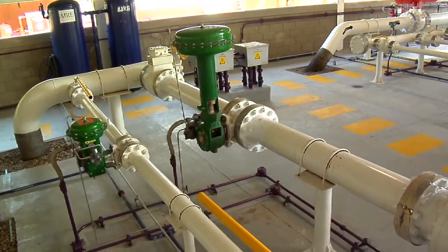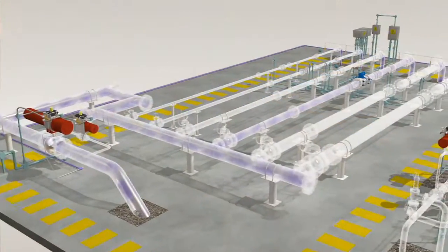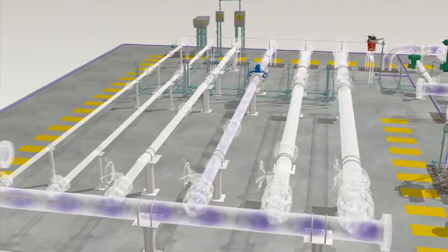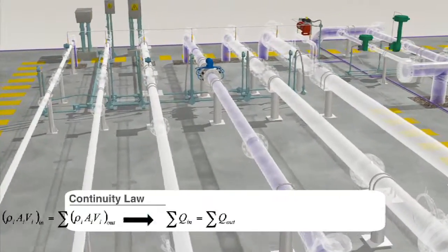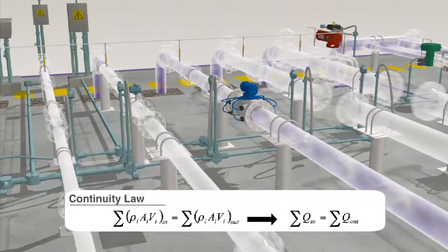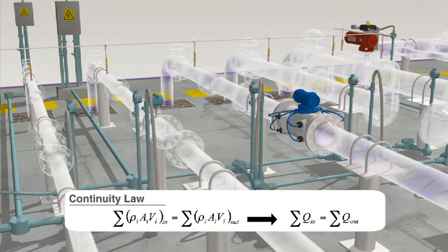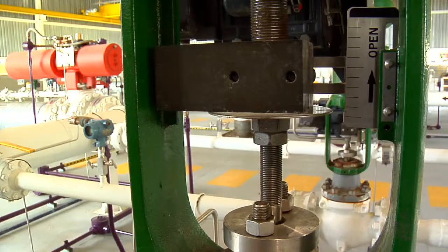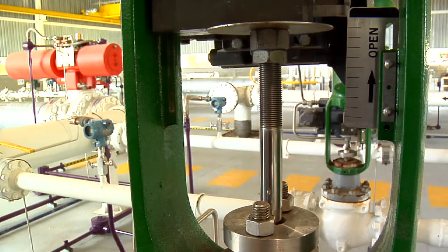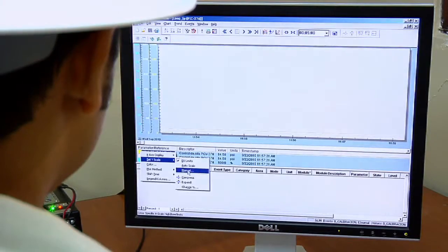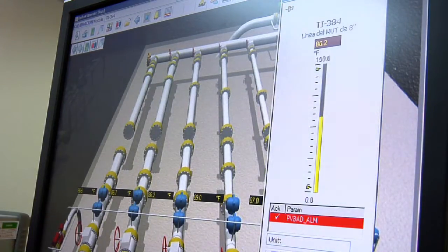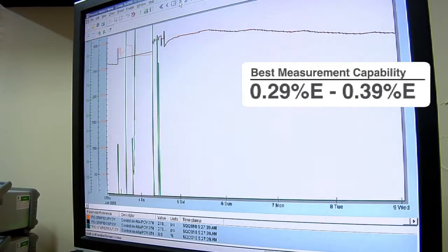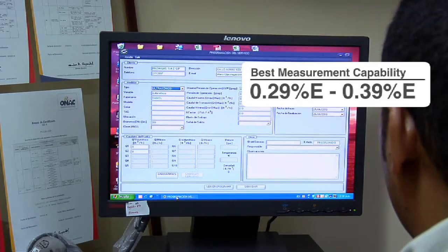The pressure, temperature and composition of fluid natural gas are constant throughout the process. This guarantees the volume of gas that enters the calibration system is equal to the volume that comes out, thereby complying with the continuity law. The calibration facility has high accuracy and repeatability instruments that ensure reliability in the measurements taken, as well as calculations and control over the variables in the process, thanks to an operational design that guarantees a best measurement capability between 0.29 and 0.39% in error measurement.